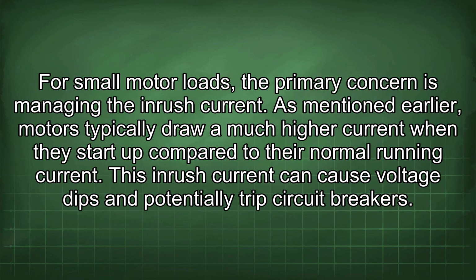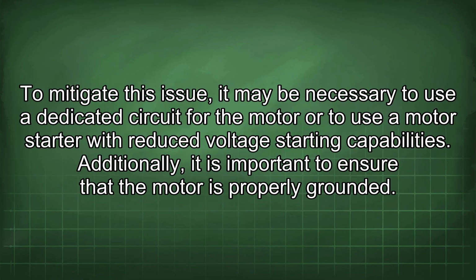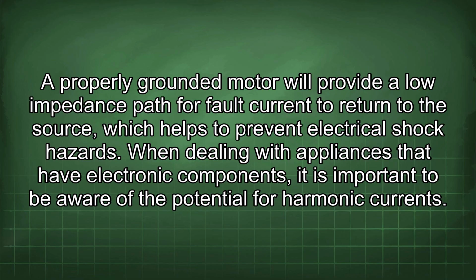For small motor loads, the primary concern is managing the inrush current. As mentioned earlier, motors typically draw a much higher current when they start up compared to their normal running current. This inrush current can cause voltage dips and potentially trip circuit breakers. To mitigate this issue, it may be necessary to use a dedicated circuit for the motor or to use a motor starter with reduced voltage starting capabilities. Additionally, it is important to ensure that the motor is properly grounded. A properly grounded motor will provide a low impedance path for fault current to return to the source, which helps to prevent electrical shock hazards.